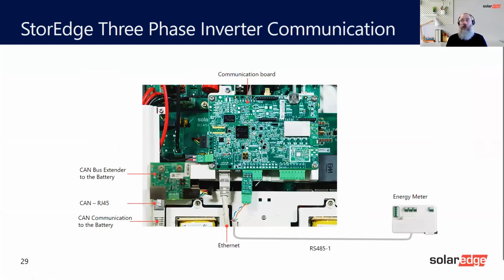So inside, you'll recognize the same communication board, no difference here. What you can see on here that is slightly different is that we've got this little bit added on, which is for the battery communication. This is CAN bus. All the cables themselves come with the equipment, so they just simply plug in. You don't have to purchase different cables of different lengths. Here is the Ethernet connection, here is the RS485 connection, and that's going to the meter here, as you can see.